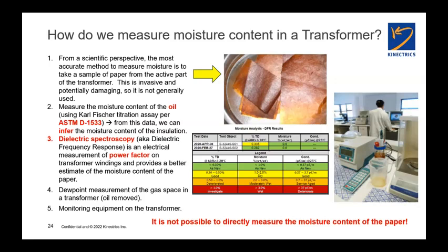From a strictly scientific perspective, and I want to emphasize that, I'm not promoting that we do this, the most accurate way to measure moisture content in a transformer is to drain the oil down, go inside, take a paper sample, and test it. That will give us the moisture content of the paper. We would put the paper in an oven, dry it down, measure it before and after the drying process, and we'd get weight by weight. Not recommended. This is very invasive. It's potentially very damaging to the transformer, and it's a lot more likely, in my opinion, that you're going to cause a problem in the transformer than solve one.